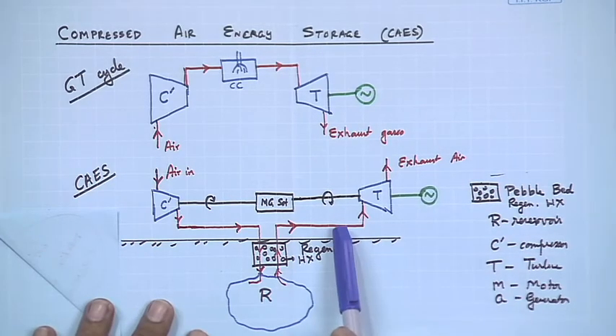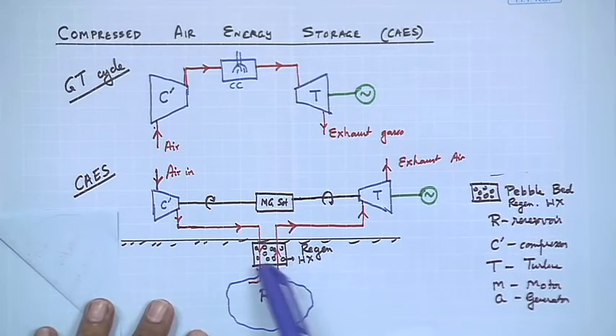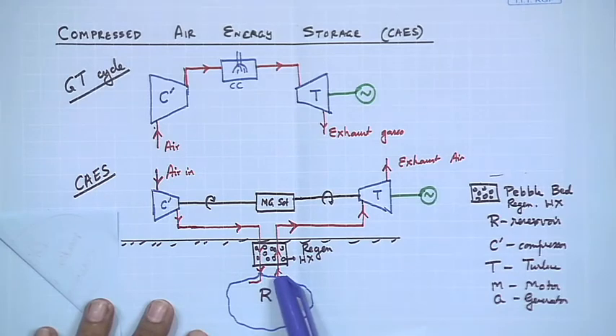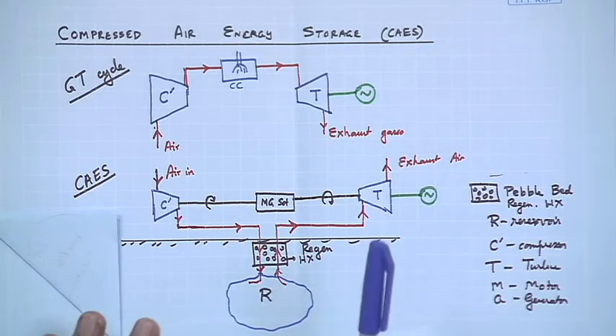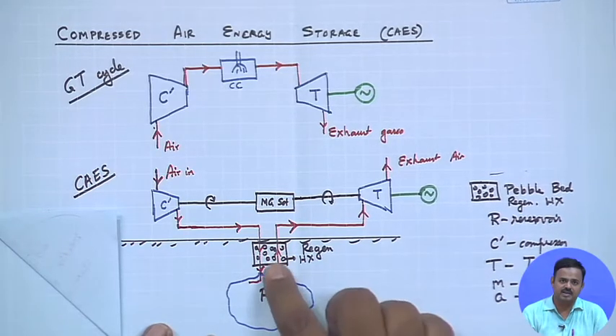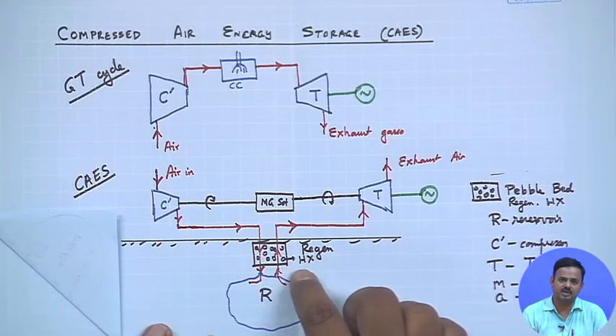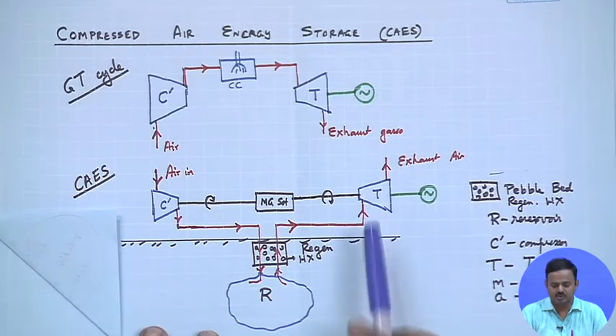This turbine is a peaking turbine that gives us additional electricity. We know that if the turbine inlet temperature is high, we get more work out of it. So we need to heat up the compressed air. This is done using a regenerative heat exchanger — a pebble bed is one example — through which the compressed air passes before storage, transferring heat to the pebble bed. When the compressed air is fed to the turbine, it first passes through this regenerative heat exchanger to heat up, then goes to the turbine.